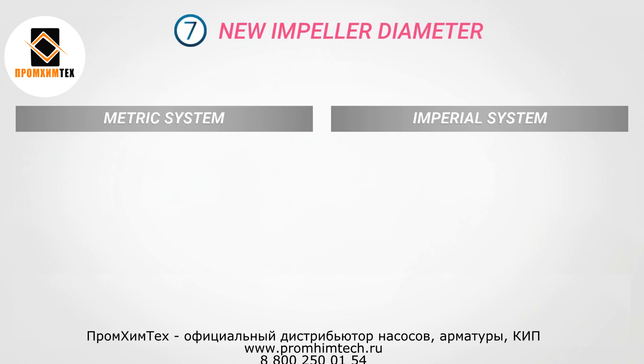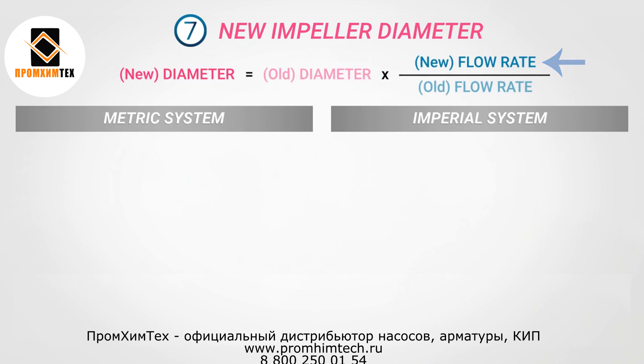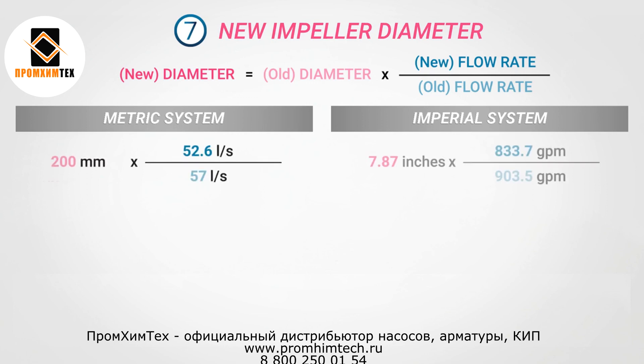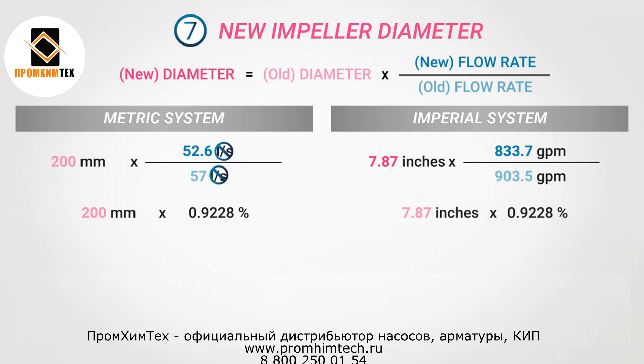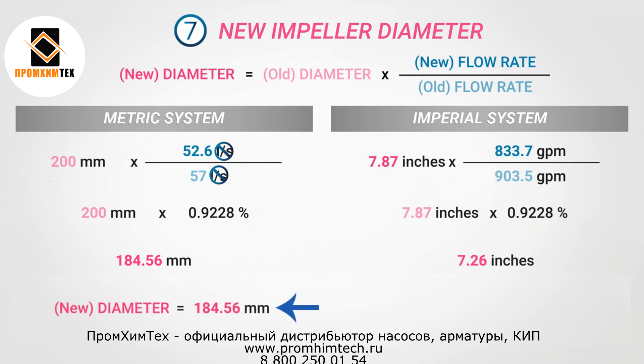In conclusion, we are going to calculate the pump impeller diameter — how much should the impeller diameter measure if we want to reach a new flow rate level? This calculation is used when the impeller is trimmed down to meet a new flow rate. The original flow rate was 57 liters per second, or 903.5 GPM. The new flow rate to reach is 52.6 liters per second, or 833.7 GPM. We cancel out the liters per second in this division to find the ratio, which we multiply by the old impeller diameter to find 184.56 mm, or 7.26 inches — the new measure of the impeller diameter.